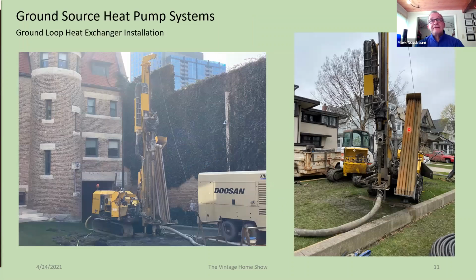Looking at how the loop field is installed, this is the most expensive piece. In our Chicago area, vertical drilling is the typical method, and there are other methods that could be talked about at other times. Some of the drill rigs are really big, huge trucks. This particular style is on tracks, and it's fairly narrow. It'll fit down an 8-foot gangway or through a 6-foot fence section pretty comfortably. It has a little bit of a head height issue. This thing folds back, but it's still maybe 10 or 12 feet tall that it has to get through.